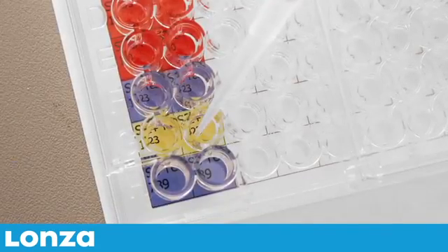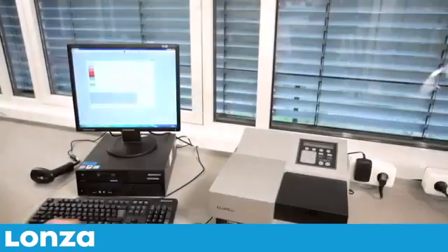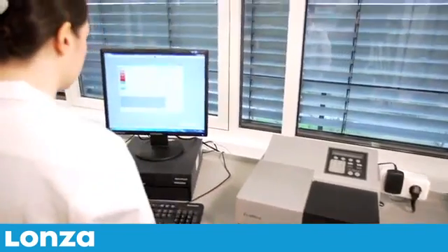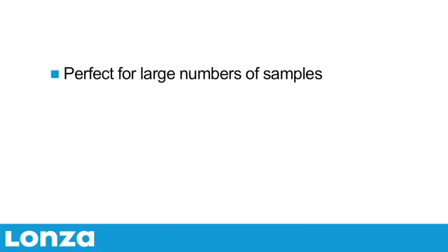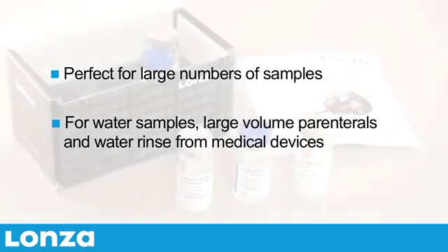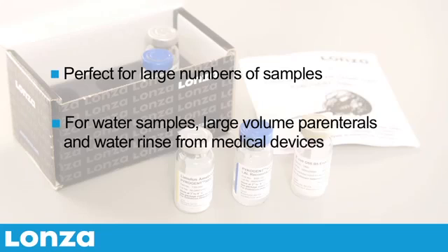A sample is mixed with the reconstituted LAL reagent in a 96-well plate, placed in the incubating absorbance plate reader, and automatically monitored over time for the appearance of turbidity. This assay is perfect for laboratories needing to process large numbers of samples. It is ideal for testing of water samples, large volume parenterals, and water rinse from medical devices.